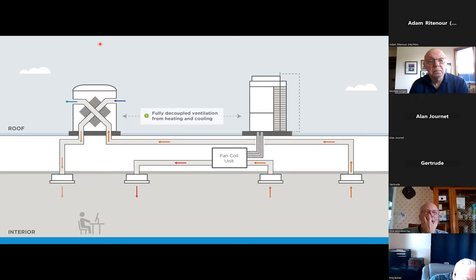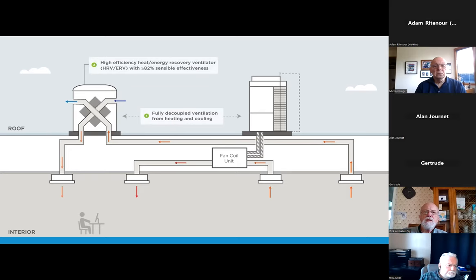So you've got a dedicated ventilation system here, and it's completely decoupled from a heating and cooling system. So neither the controls nor the ducts cross for these two systems. The second key component to a VHE DOAS system is the high efficiency heat or energy recovery ventilator, HRV or ERV. And I'll probably use those interchangeably in this presentation, but we're talking about an energy recovery ventilator with greater than or equal to 82% sensible effectiveness.